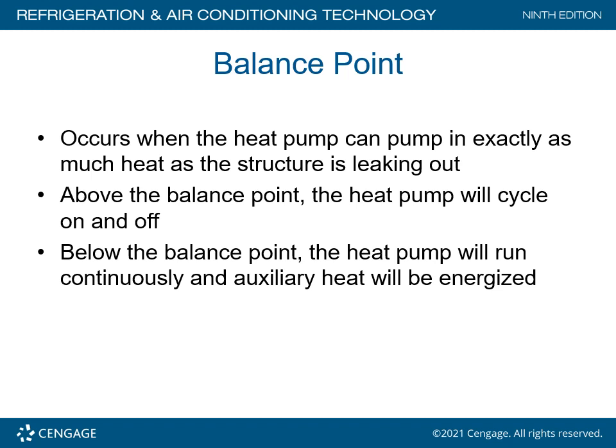Anyways, the balance point occurs when the heat pump can pump in exactly as much heat to the structure as is leaking out. Above the balance point, the heat pump will cycle on and off. Below the balance point, the heat pump will run and run and run. Auxiliary heat will be energized.